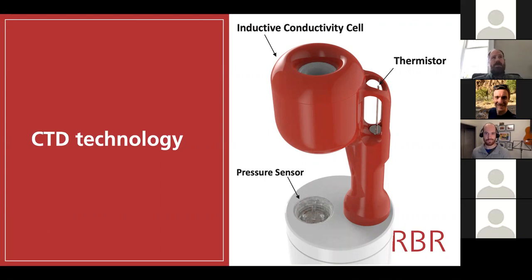And of course, conductivity is not actually really the ocean variable that we're interested in. We're typically interested at the end of the day in density. And on the way there, we might be interested in salinity. But conductivity on its own doesn't particularly measure anything useful in the abstract sense. In order to use, for instance, the practical salinity scale from 1978, PSS-78, or TEOS-10, which is a more interesting kind of absolute measure of salinity, you really need to be assessing both conductivity and temperature together. And there's a very strong dependence of salinity on temperature, as you know. And so it's important that both of those measurements are not only accurate, but taken at the same time and in the same place.